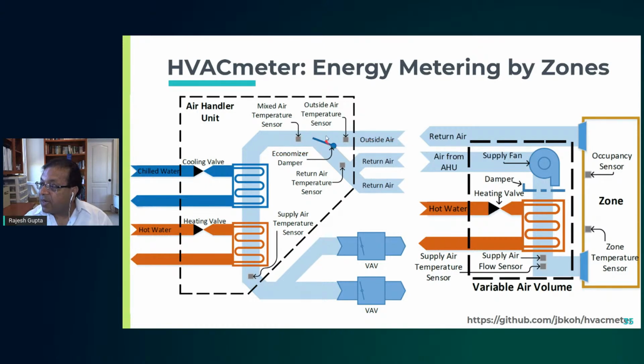So depending upon how you set the economizer, you can change the fraction of air that is coming from the return of the building to the outside air. Of course, in infection control days, you want to minimize the return air and maximize outside air. But that takes more energy, though. Similarly, on the supply side, you have supply sensors that are going to each of these VAVs, and a VAV looks like this, which has its own sensors, the flow sensors. So you can even start to imagine that if I'm measuring supply air temperature, and then I'm measuring the temperature being seen by each of the VAVs, I can start to get a picture as to what the heat loss is in different zones, for example.